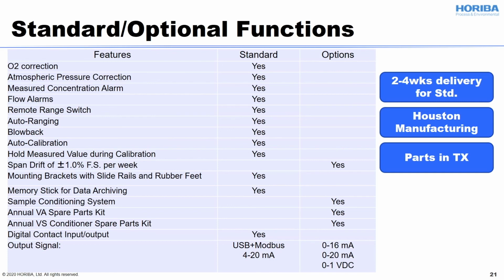Alright, this is just for information on the spec. Most of the functions are in the standard spec, such as O2 correction, atmospheric pressure correction, concentration alarm, flow alarm, remote range switch, auto range switch, blowback, auto calibration, and hold measured value during the calibration. Digital contact inputs and outputs and analog outputs, and Modbus TCP/IP communications. You may want to consider additional sampling systems if you don't have any sampling unit. The lead time is really quick. Our standard lead time is about 2 to 4 weeks for standard manufacturing. All of the parts are located in the Houston factory too.